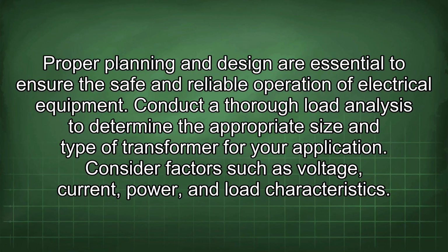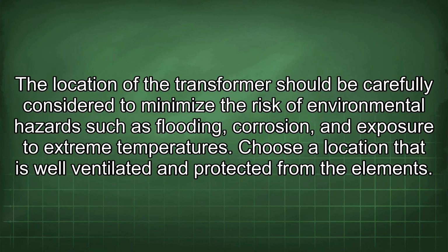Conduct a thorough load analysis to determine the appropriate size and type of transformer for your application. Consider factors such as voltage, current, power, and load characteristics. The location of the transformer should be carefully considered to minimize the risk of environmental hazards such as flooding, corrosion, and exposure to extreme temperatures. Choose a location that is well ventilated and protected from the elements.